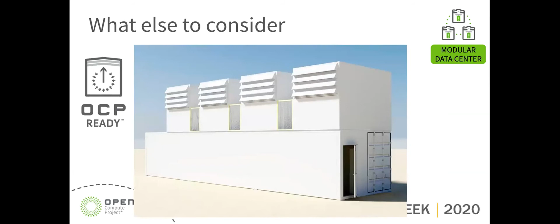This is an example of an HPC module. Traditionally, if we looked at the first module from PCX and Schneider, they had a 90 kilowatt specification, but it's relatively easy to go for the same floor space to 100, 200, or even 500 kilowatts. So we also need to consider drastically higher load densities within a module.